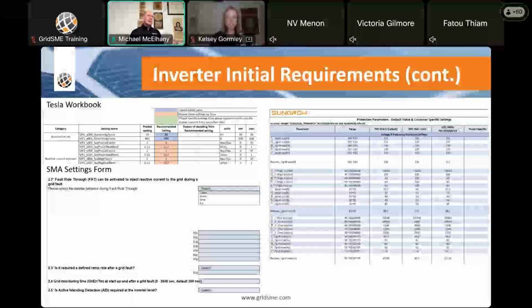The SMA settings, here's fault ride through to be activated. Their mode is for full, that's full reactive capability. That's the one we want to go with for CAISO. So I just kind of pulled that piece of it out.